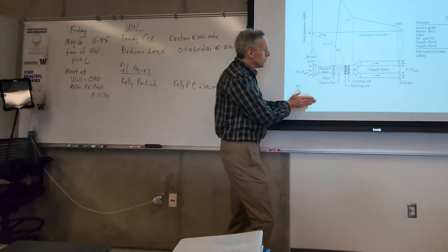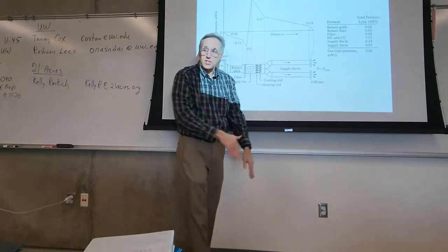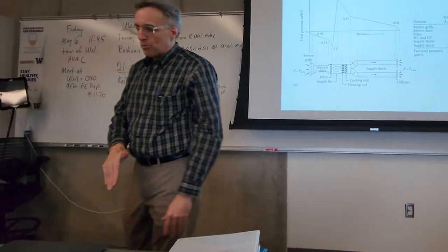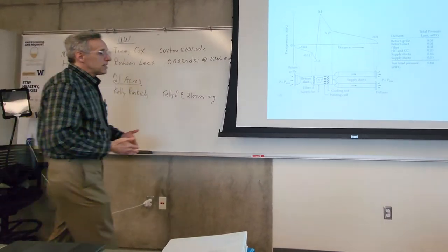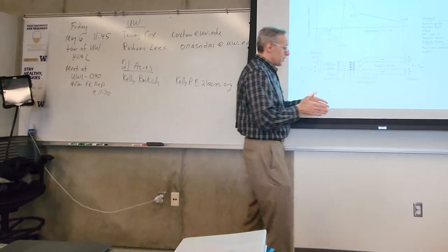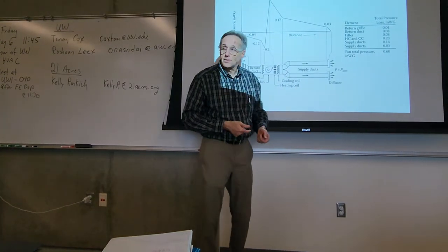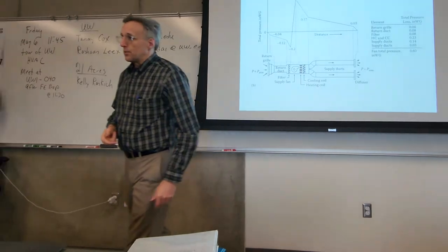When you expand the flow, the opposite happens. The static pressure will increase, and the velocity pressure goes down. By static regain, what that means is that you're expanding the flow to allow the static pressure to come up. You're trading off the velocity head for static head.